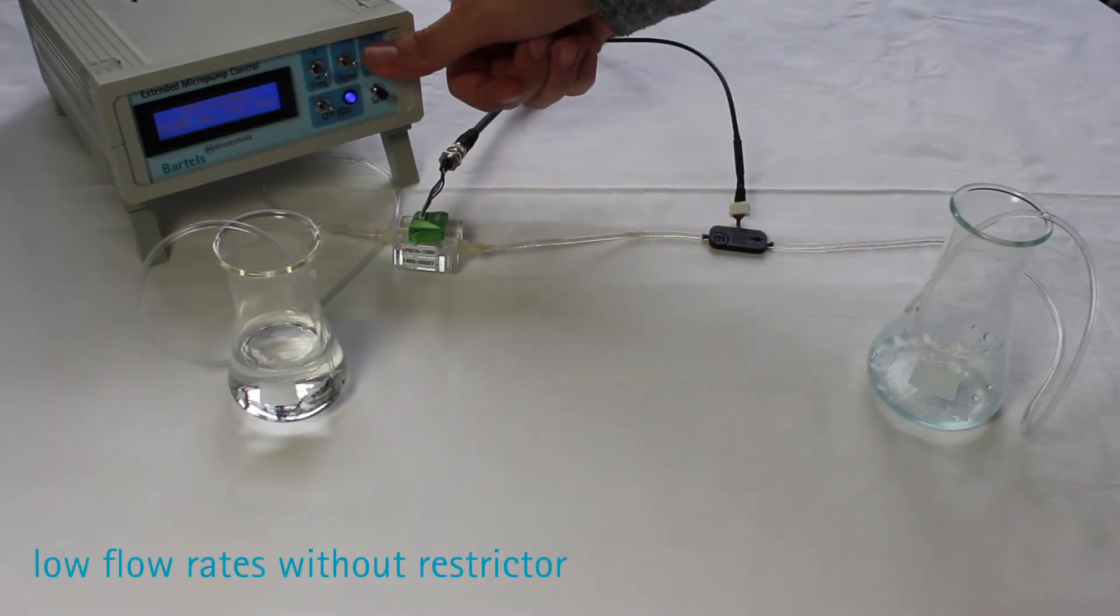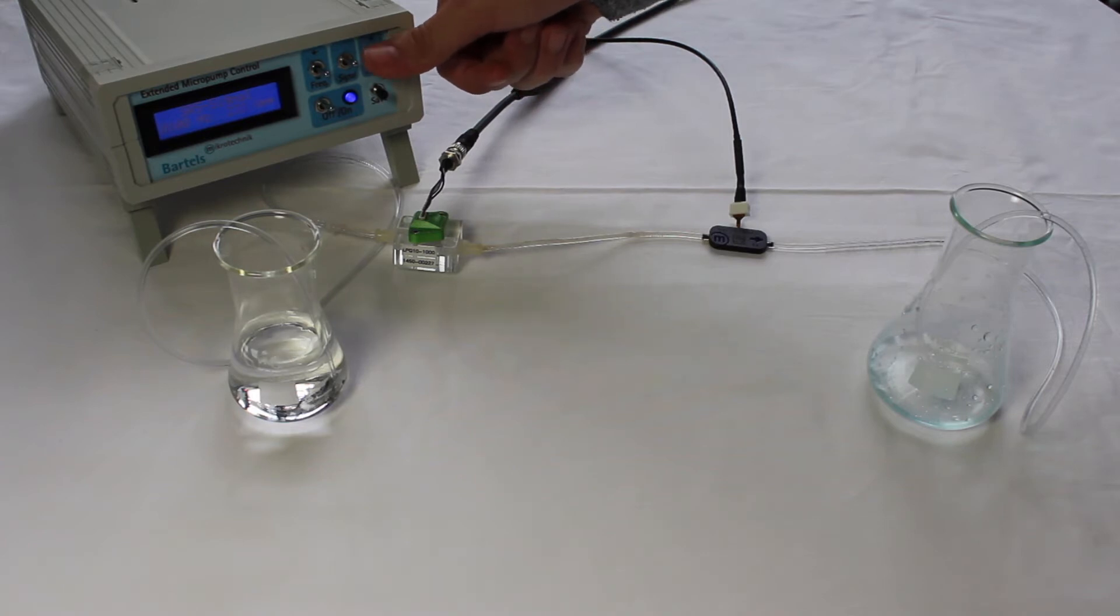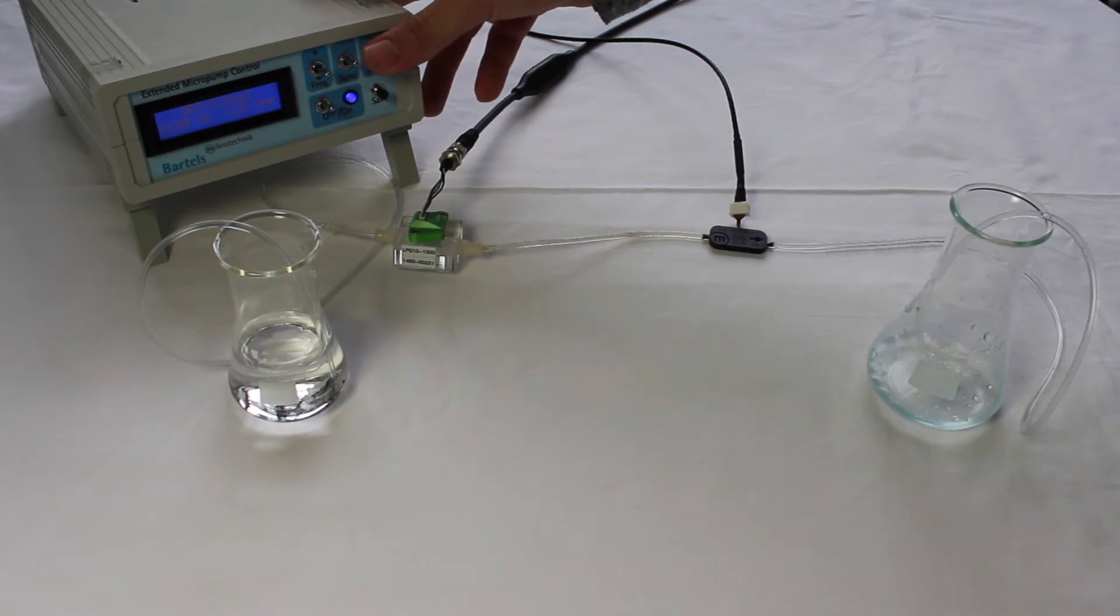A simple method to achieve low flow rates is lowering the amplitude, which on the other hand will decrease the overall performance of the pump because the typical pump curve of volume flow over pressure will then be shifted to a parallel curve.